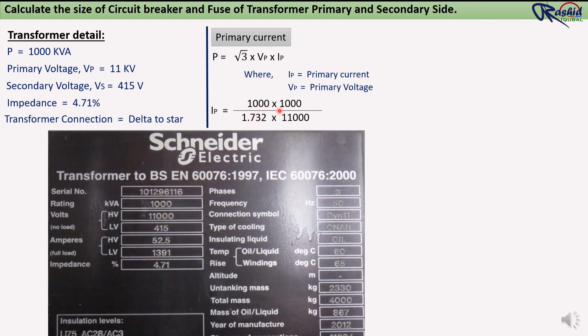Now Ip = 1000 kVA — to convert kVA to VA we multiply by 1000 — divided by 1.73 multiplied by the primary voltage of 11,000 volts. After solving this equation, we get 52.49 ampere. This is the primary current of the transformer.